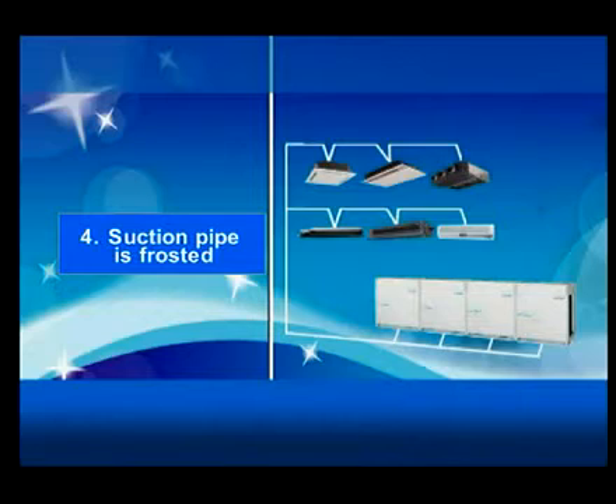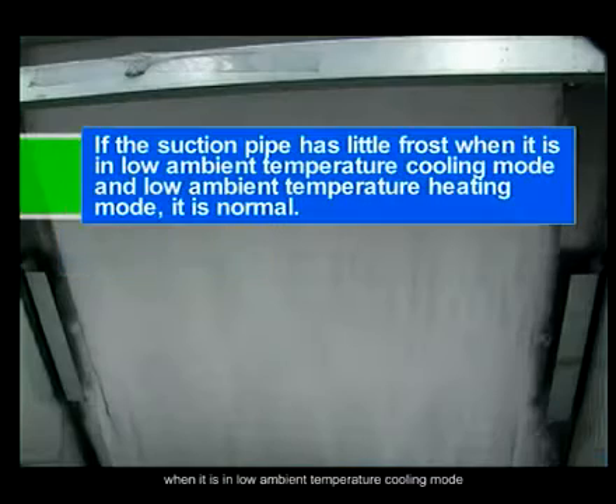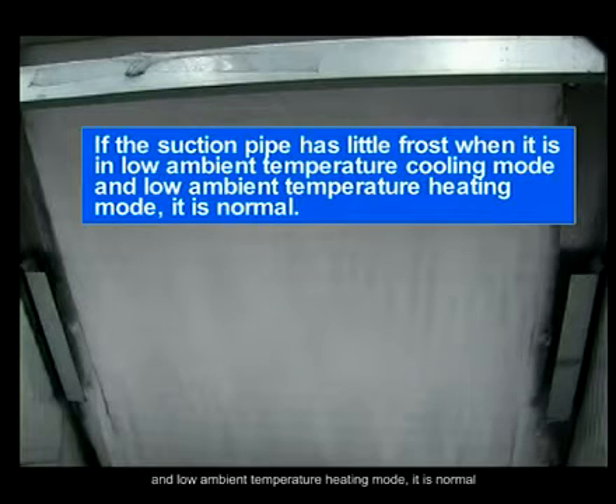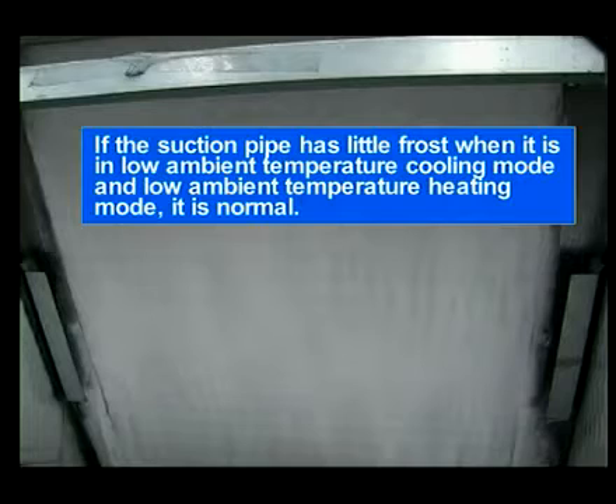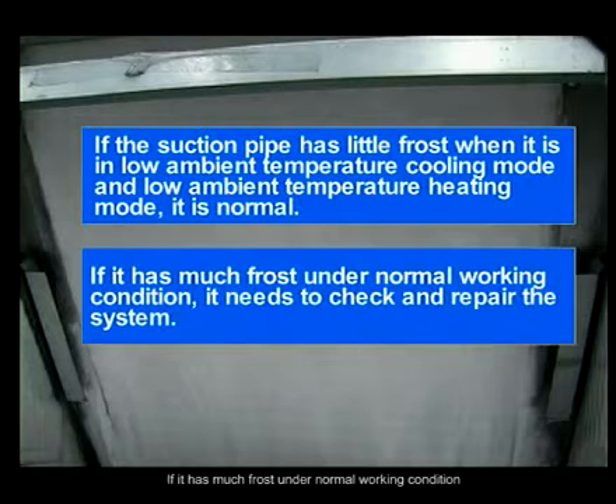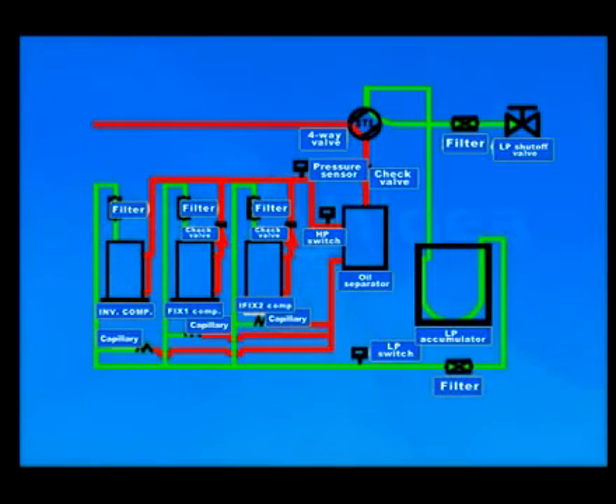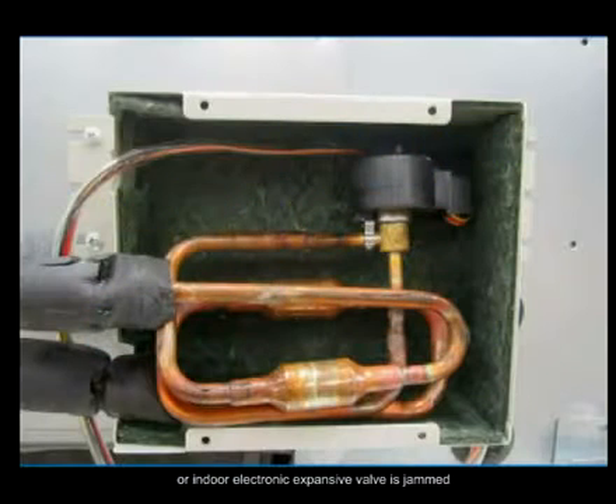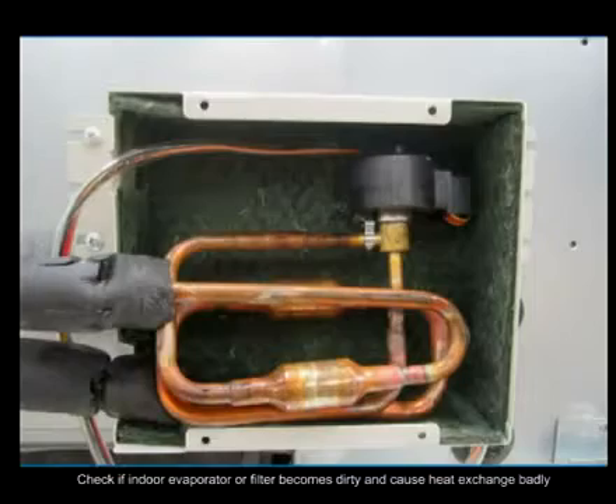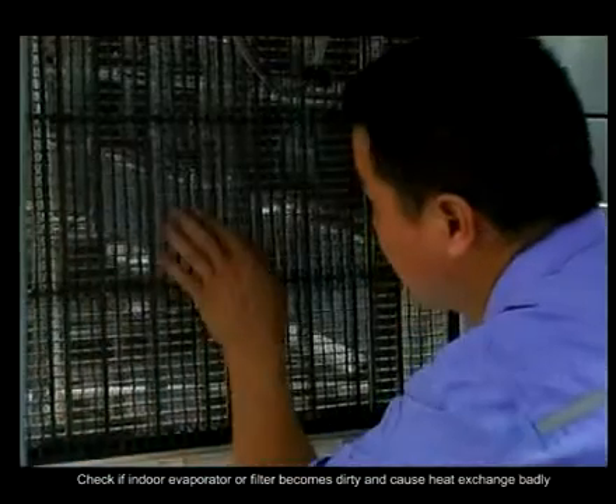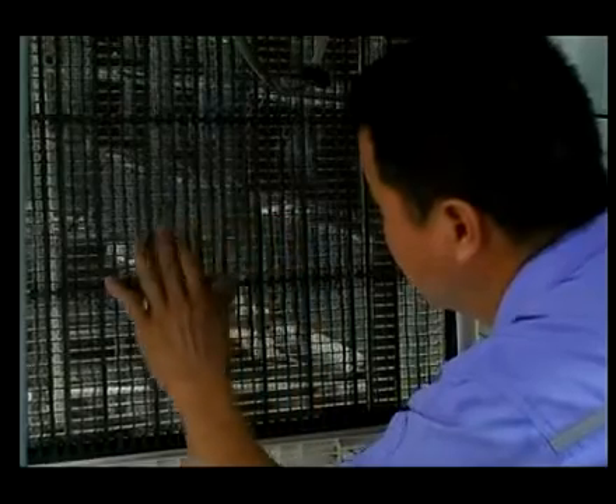Suction pipe is frosted. If the suction pipe has little frost when it is in low ambient temperature cooling mode and low ambient temperature heating mode, it is normal. If it has much frost under normal working condition, it needs to be checked and the system repaired. Repair instructions of suction pipe frosting. Step 1. Check if the filter of the low pressure side or the indoor electronic expansion valve is jammed. Check if the indoor evaporator or filter has become dirty and causes bad heat exchange.